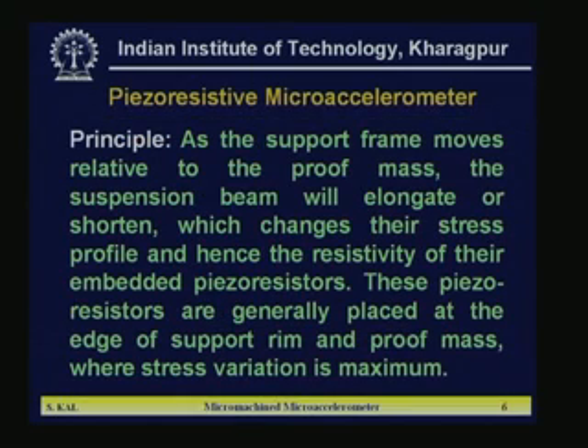Next, the principle is as I just told you. As the support frame moves relative to the proof mass, the suspension beam will elongate or shorten, which changes their stress profile and hence the resistivity of their embedded piezoresistors. These piezoresistors are generally placed at the edge of the support rim and proof mass, where the stress variation is maximum.